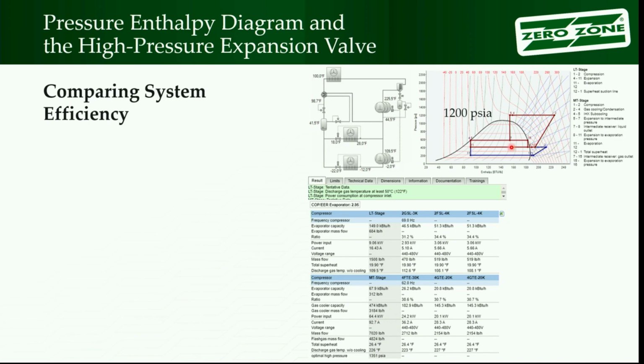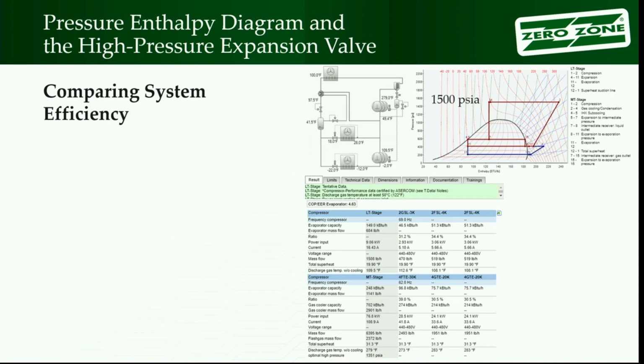We'll see in these tables when we get to the end, we'll have those together so we can see how dramatic that is. And how bad it would be if you thought, boy, let's drop the head like we've always done, lower that pressure and think I'm going to do better, and then you're wondering why the suction pressures keep going up. So if you did that and noticed things got bad and said, well, I can always reverse, you know, go one way, turns out bad, turn around and try the other way. I'm going to raise up my pressure. I'm going to go up to 1500 psi.